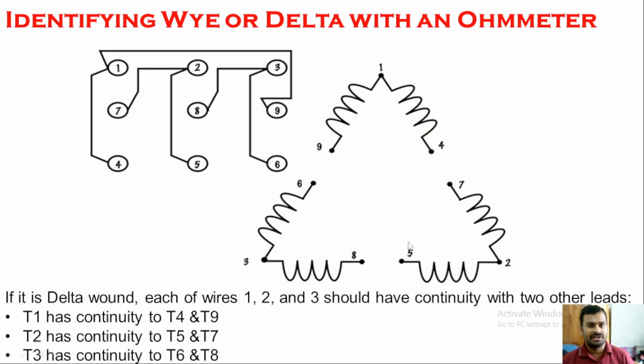So for delta configuration, in a similar way, we are going to follow the same methodology. We take the Ohmmeter and measure the resistance. Now the only difference is, with respect to any one terminal, you will get 2 values. So 1 and 4 you get a value, and 1 and 9 also you get a value. In the previous case, only with respect to one terminal I got the resistance, not the other 2 terminals. But now, in one terminal I get 2 values of resistance.